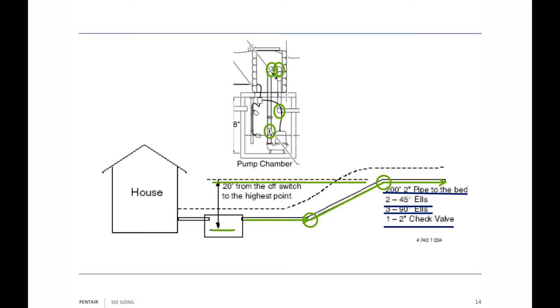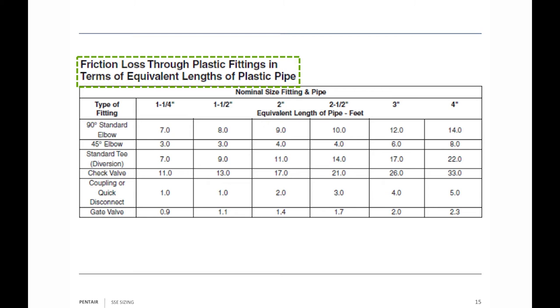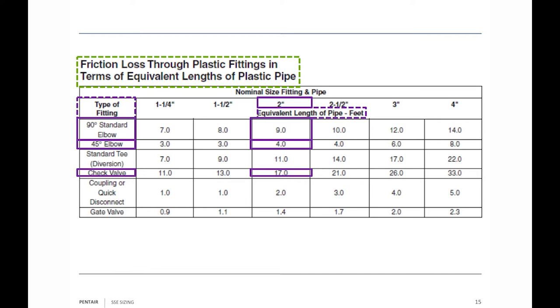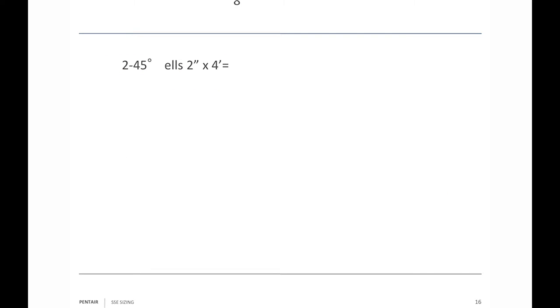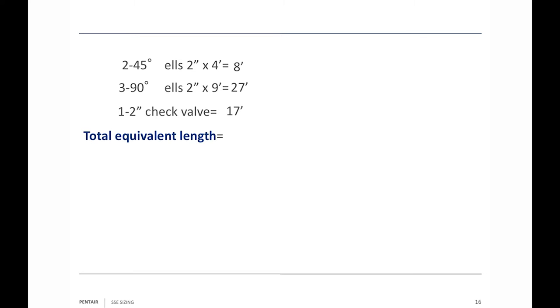From the off switch to the highest point we have to pump the water is 20 feet. Using the friction loss through fittings table — equivalent length of pipe — a standard 90° two-inch fitting equals 9 feet of straight pipe; a 45° two-inch equals 4 feet; a check valve equals 17 feet. Two 45s = 8 feet, three 90s = 27 feet, one check valve = 17 feet. Total equivalent pipe length for fittings: 52 feet.